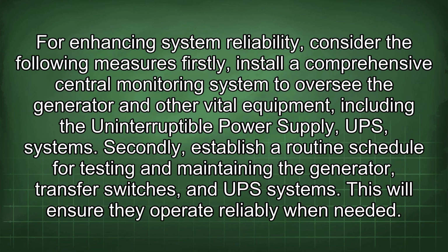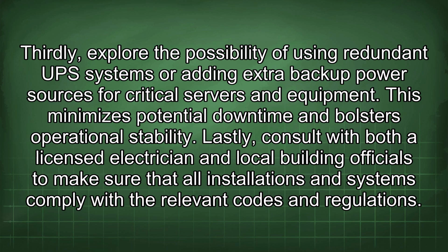For enhancing system reliability, consider the following measures. Firstly, install a comprehensive central monitoring system to oversee the generator and other vital equipment, including the uninterruptible power supply (UPS) systems. Secondly, establish a routine schedule for testing and maintaining the generator, transfer switches, and UPS systems. This will ensure they operate reliably when needed. Thirdly, explore the possibility of using redundant UPS systems or adding extra backup power sources for critical servers and equipment. This minimizes potential downtime and bolsters operational stability.